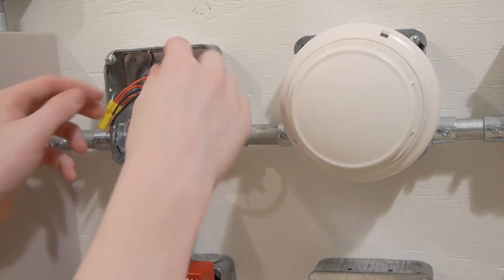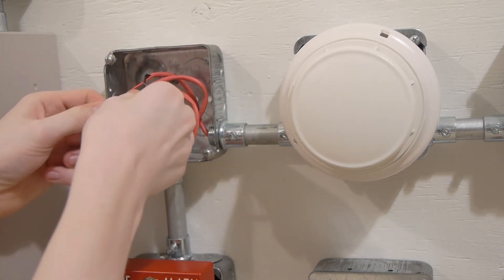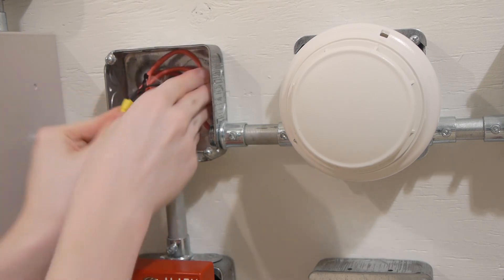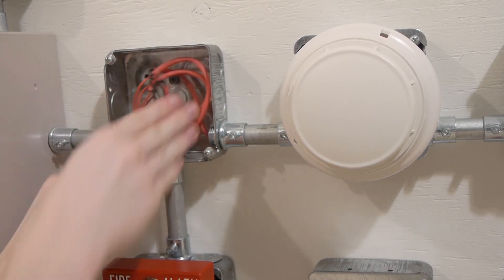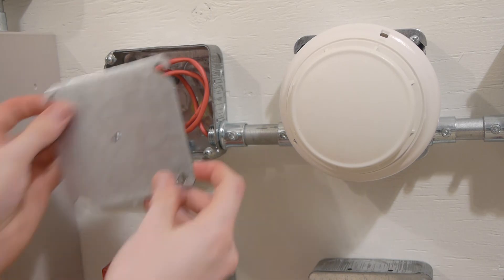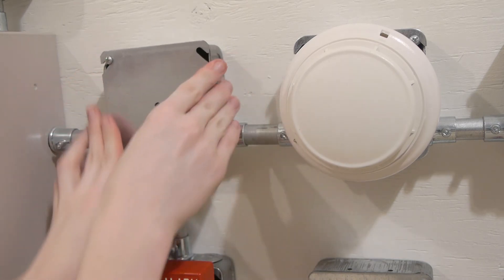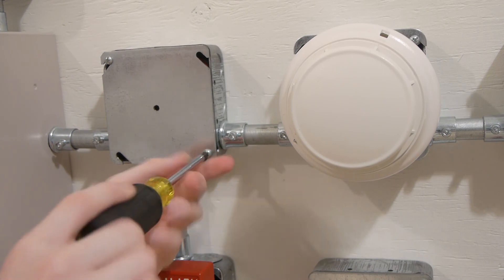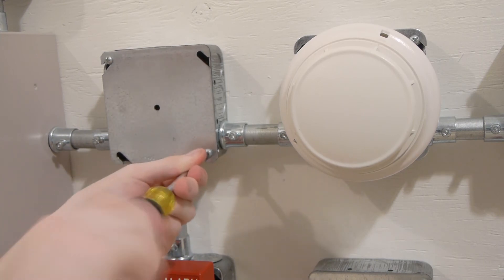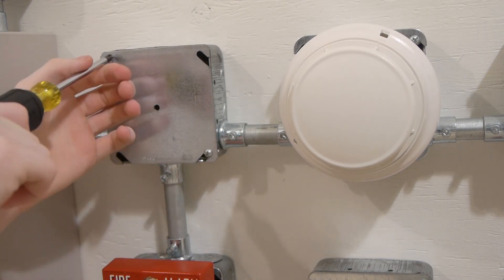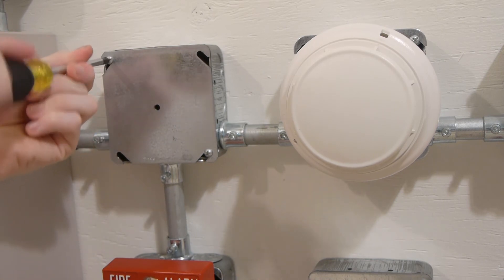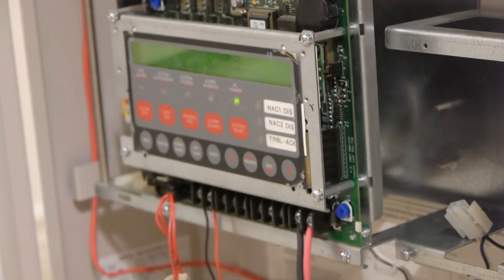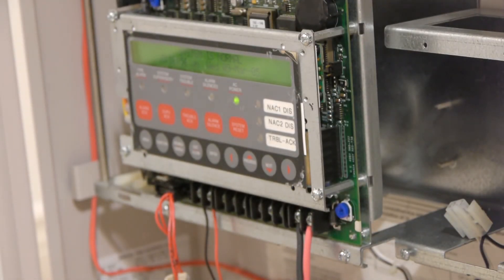Now keep in mind there might be multiple ground faults on the system, especially if it's a large system. So I can go ahead and put that back in the box and put the cover back on, tighten it down. If we go back to the panel, as you can see there are no troubles, which means we have fixed the ground fault.